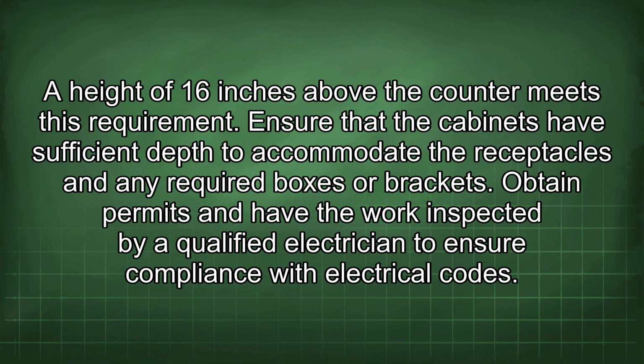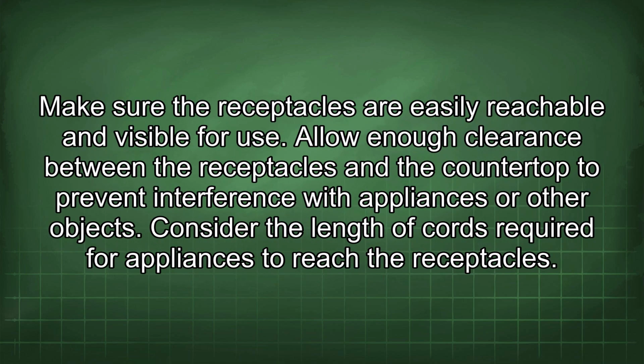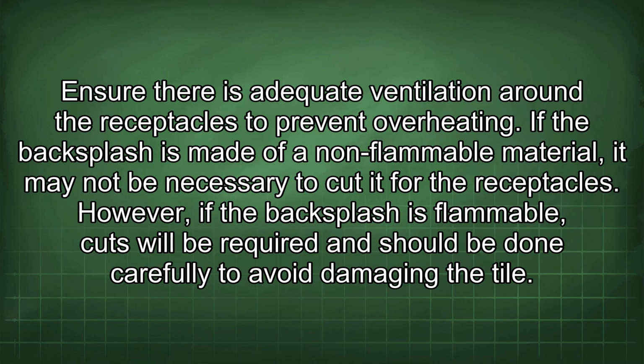Obtain permits and have the work inspected by a qualified electrician to ensure compliance with electrical codes. Make sure the receptacles are easily reachable and visible for use. Allow enough clearance between the receptacles and the countertop to prevent interference with appliances or other objects. Consider the length of cord required for appliances to reach the receptacles. Ensure there is adequate ventilation around the receptacles to prevent overheating.